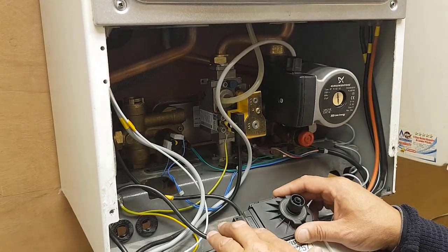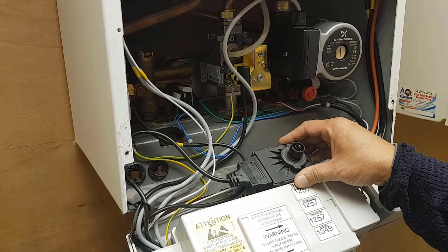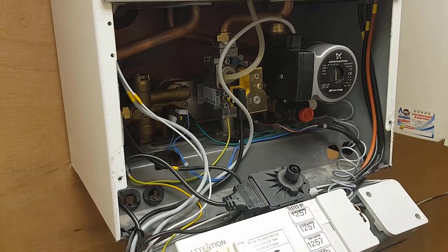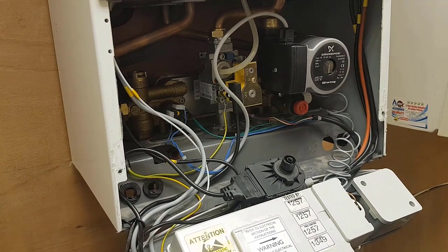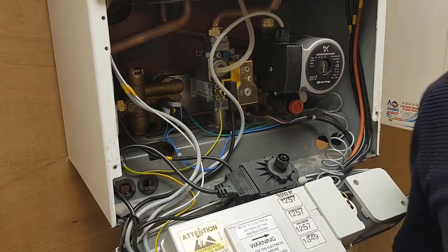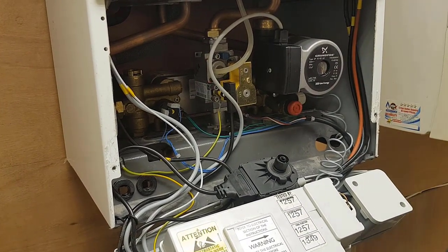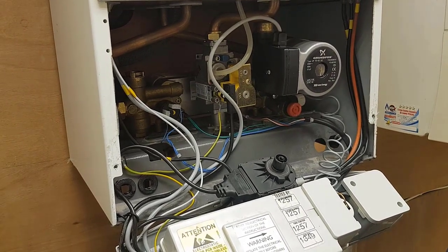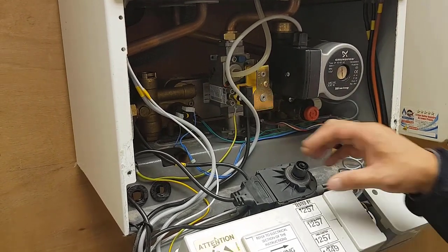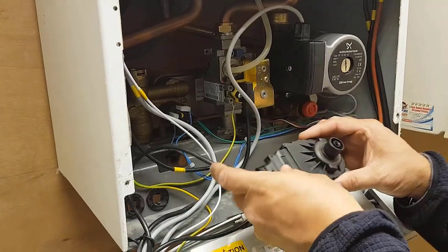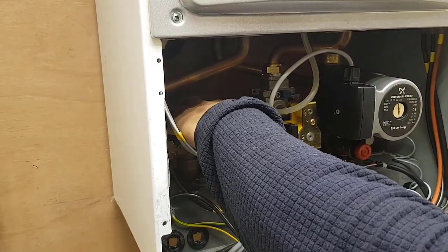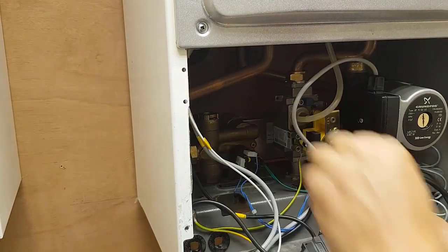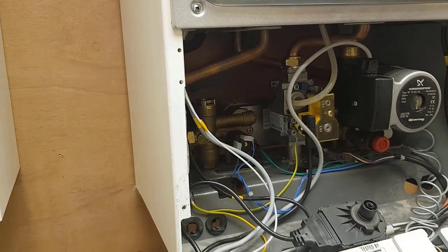Right, okay. I've diagnosed what the fault is. I'm now going to tell the customer what the issue is with the boiler. Right, Mr. Morgan, I've diagnosed what the fault is. There's a fault with the actuator motor. Water's gone into it, and there's water inside the diverter valve cartridge, so we'll have to replace them.